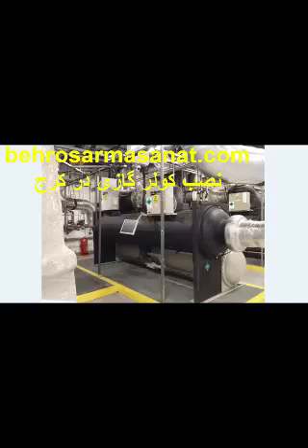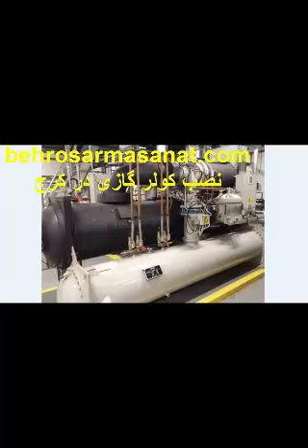And if we look at the back of this chiller, there's the condenser again there, and you'll see this pipe coming along from there, because that chilled water costs quite a lot of money to produce, so you want to retain as much coolth in that water as possible. So the chilled water is entering and leaving here. It's entering at about 12 degrees and it's coming back out at about 6 degrees Celsius.